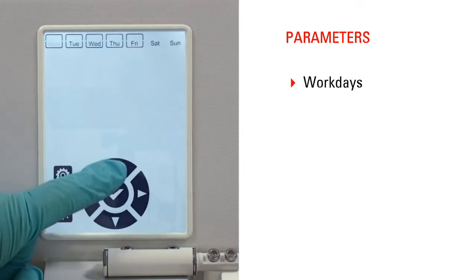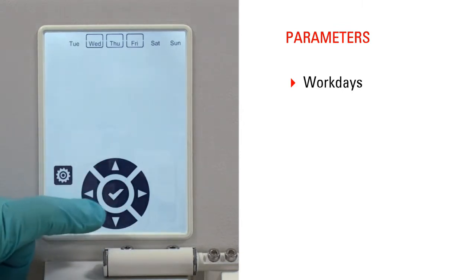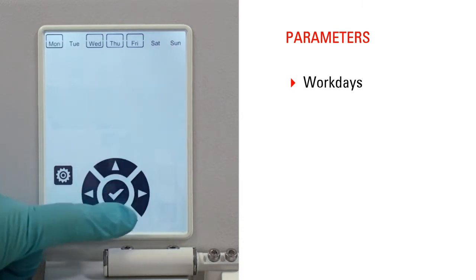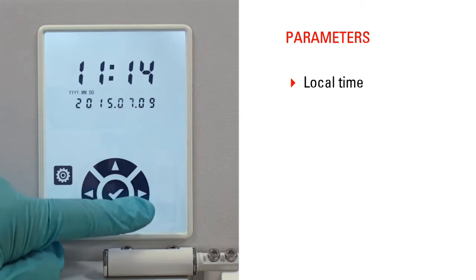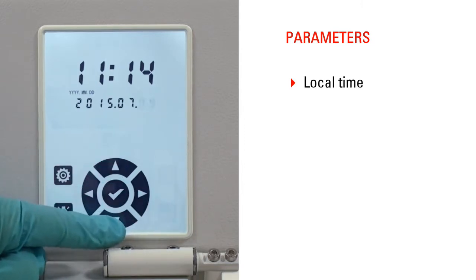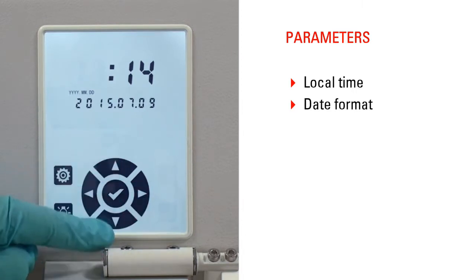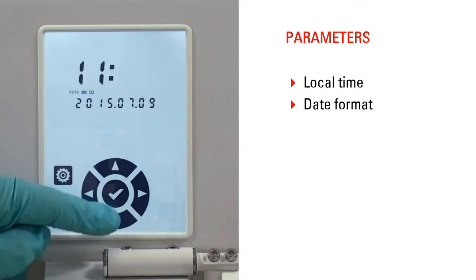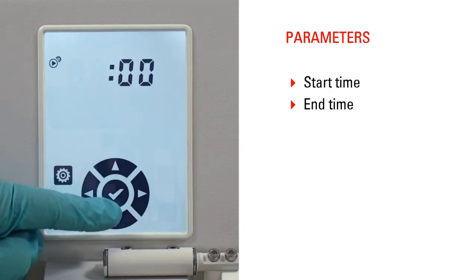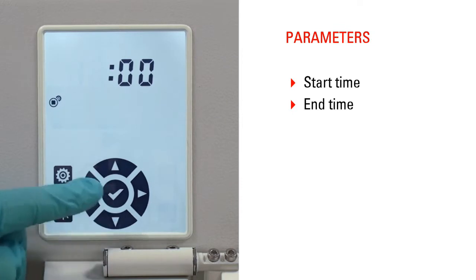Workdays and times can be programmed for automatic instrument operation. The date and time shown on the control panel must be set to the current local time to ensure correct operation of the time program control. An automatic switch on feature is linked to individual predefined workdays. The preferred date format can be selected. On weekdays that have been defined as workdays, the instrument will be heated up to the required temperatures in time and is ready to operate when needed.